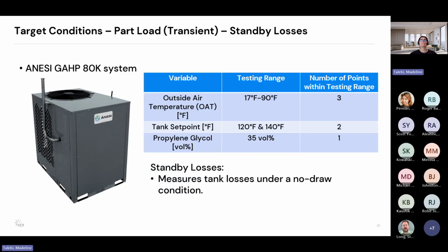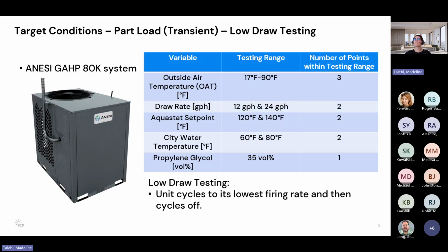And so the part load testing was set up in 3 different types of testing. First, looking at standby losses, so measuring the tank losses under a no draw condition, modulating the system as it is configured and leveraging some of its modulating capabilities. So again, the first one was standby testing. Then a low draw testing, essentially waiting for the unit to cycle to its lowest firing rate and then completely cycling off. I have those different testing points that were looked at for this type of testing.